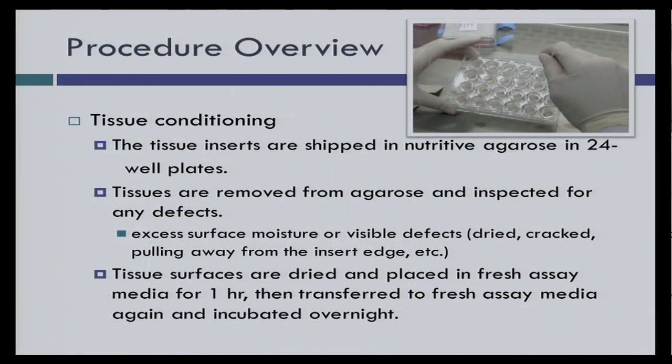Compared to the four-week animal test costing ~$1,300, the in vitro irritation test takes only a couple of weeks and will eventually be cheaper. Nelson Labs has this test validated, so we can run it now, but currently it can only be submitted to European regulatory agencies. To run the test: we extract in polar and non-polar solvents, receive the RhE tissues, inspect them for damage, place them on fresh media overnight to prepare, then topically apply 100 µL of your extract in triplicate.